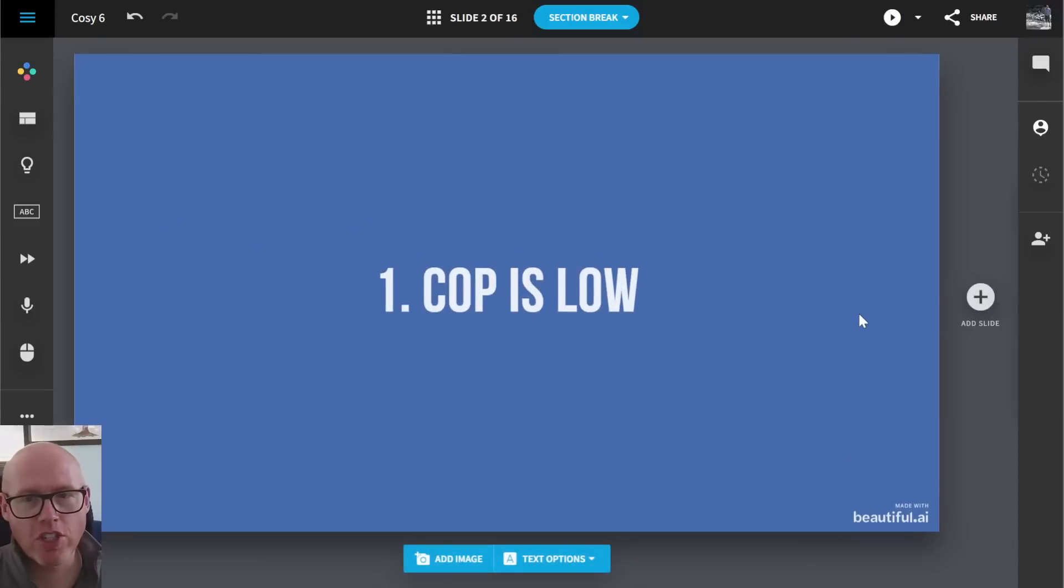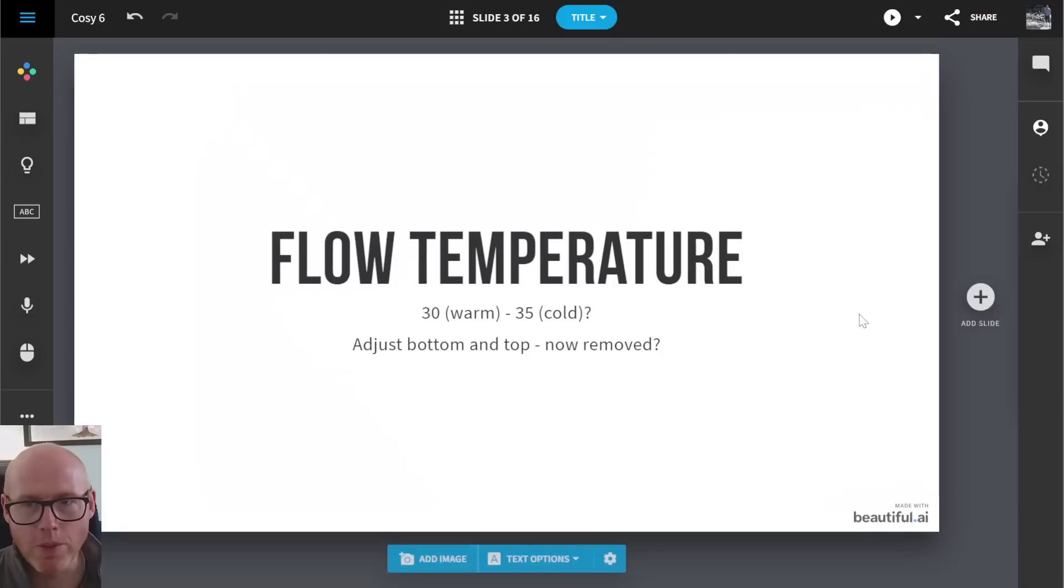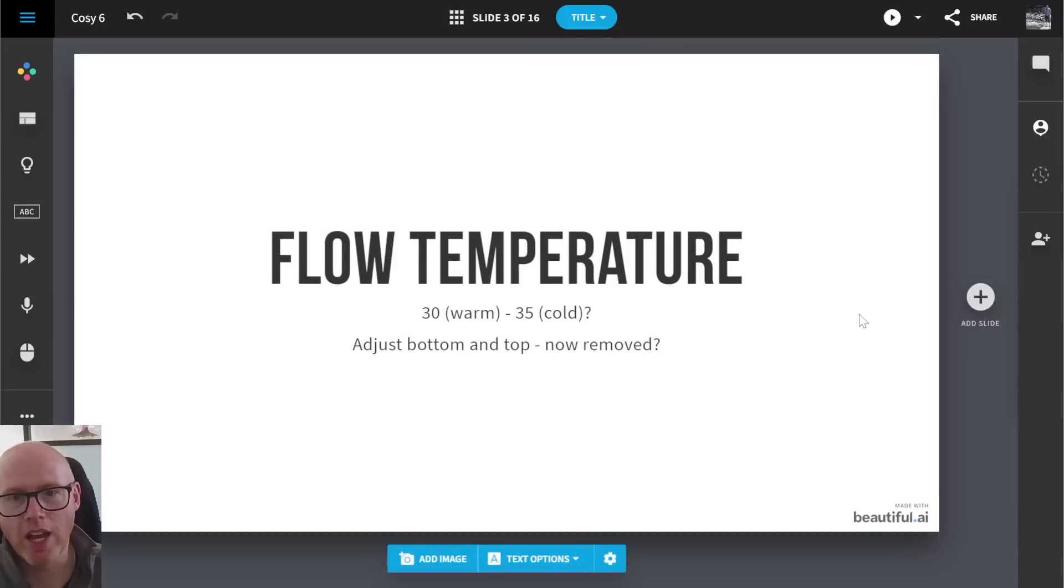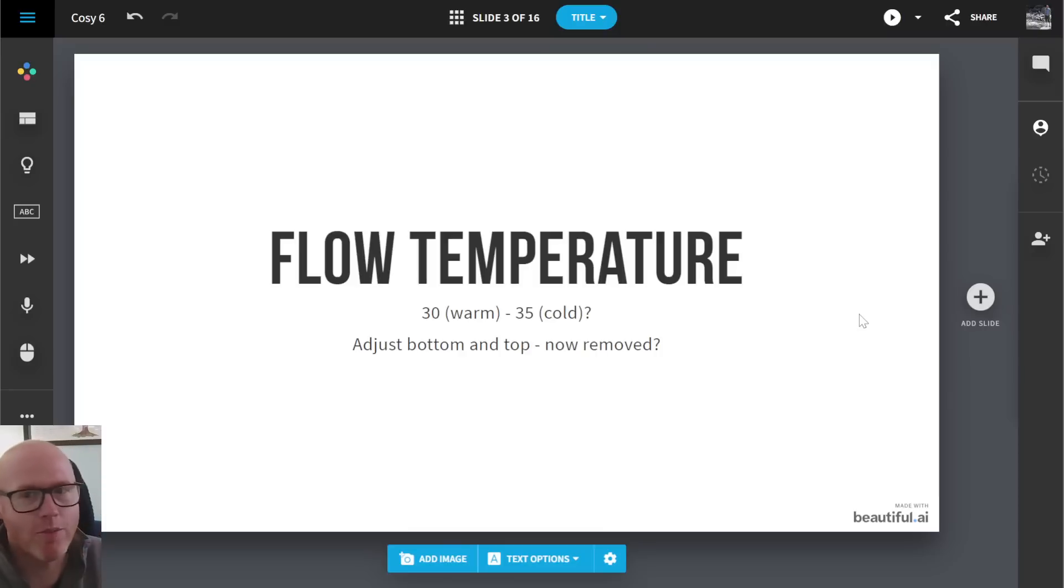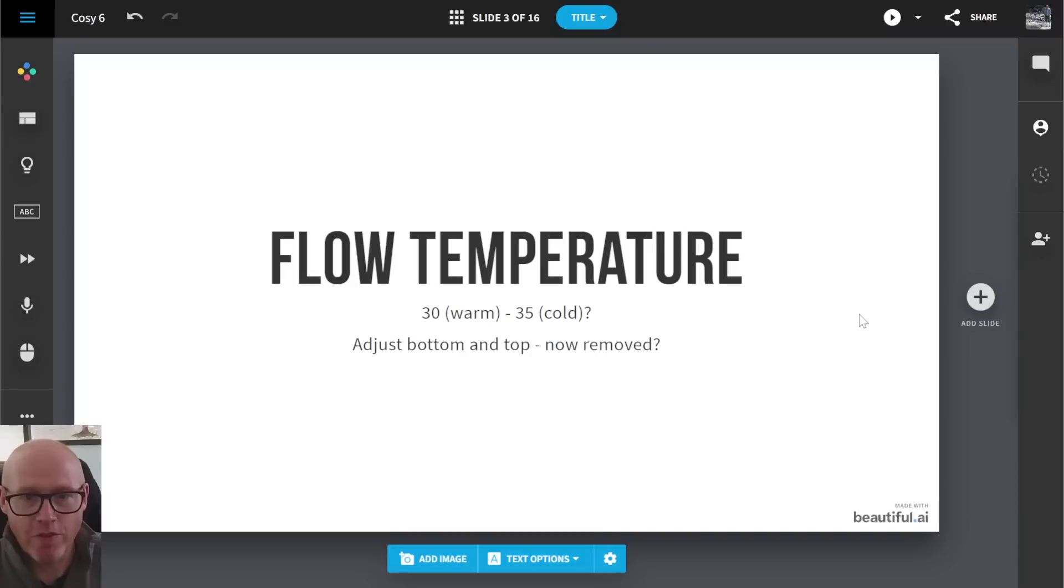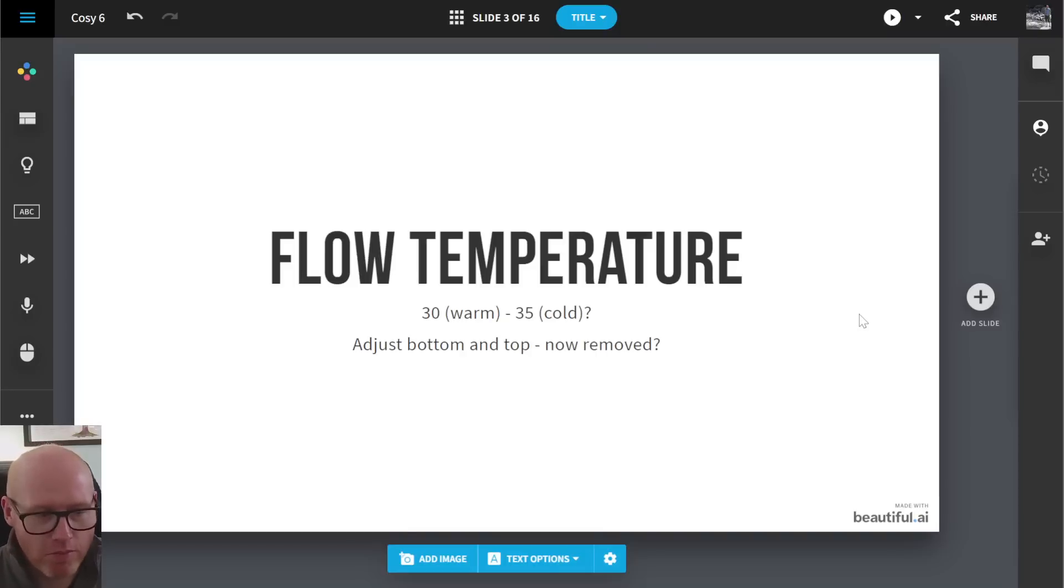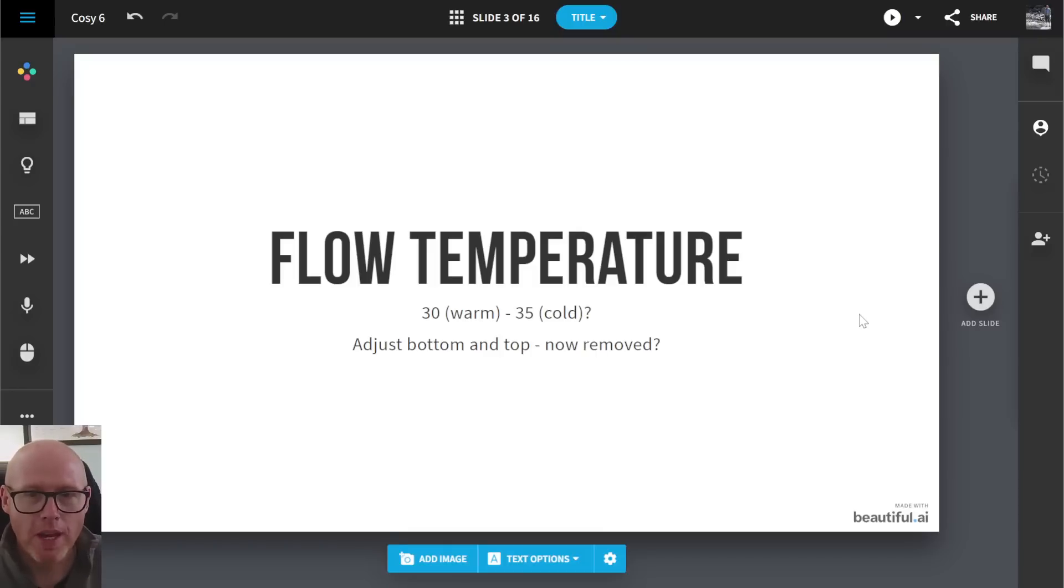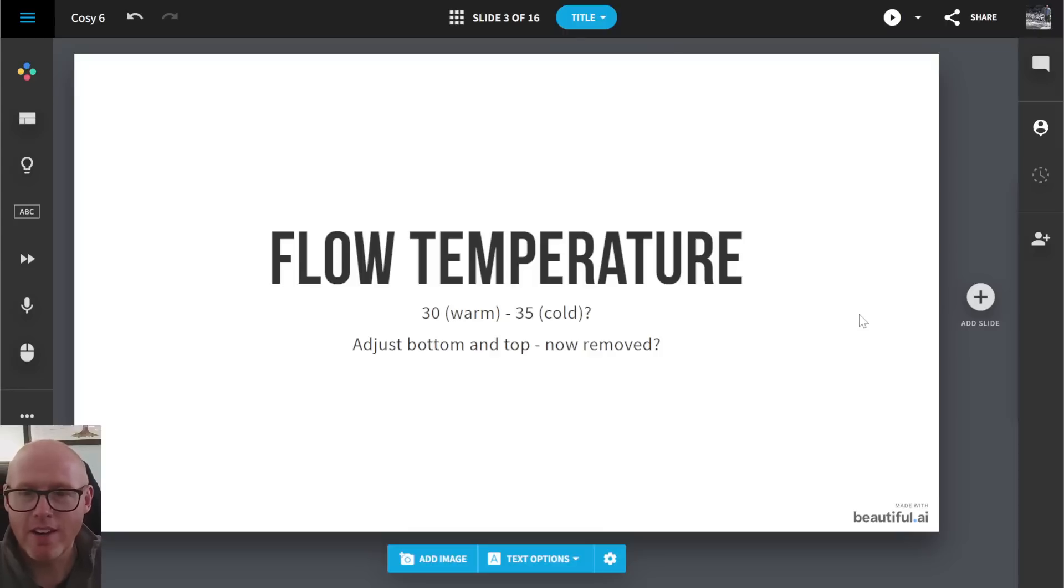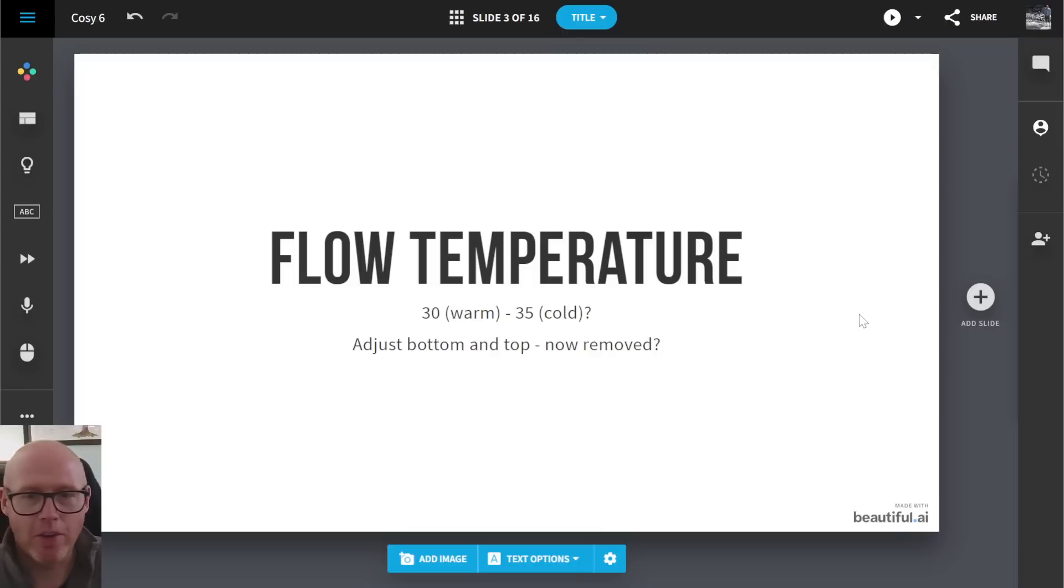So the first issue was that the COP was low. This was mainly because of flow temperature and because Nick had basically tweaked it too low. And I know previously in my other video I said low flow temperature is always better. But for the physical heat pump itself, if it can basically get rid of all of that heat that it's trying to pump in the system, then yes, that's fine. But if your house is already warm and your radiators can't shed that heat into the building, then there's no point going low with a flow temperature and you will end up with cycling and everything else.